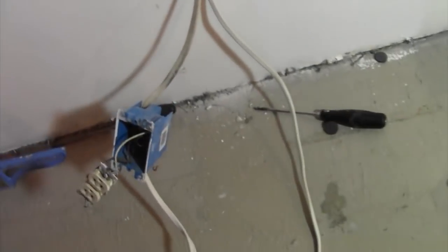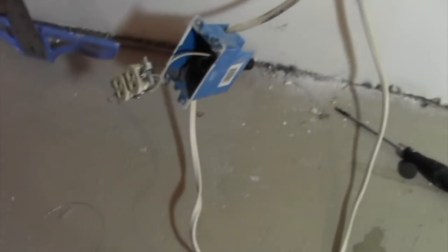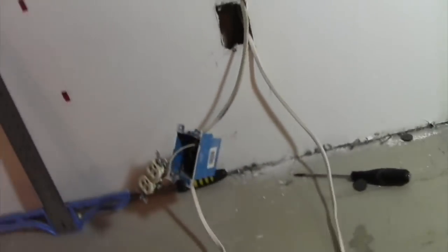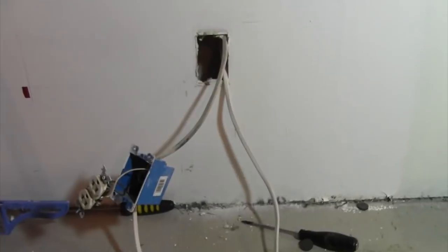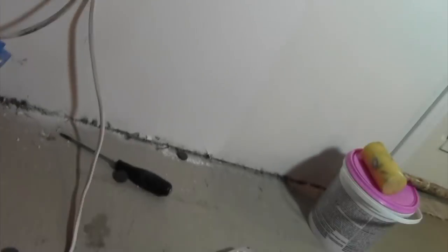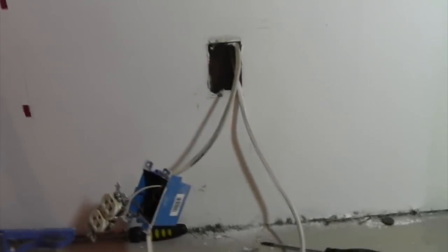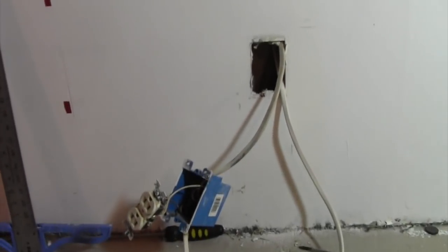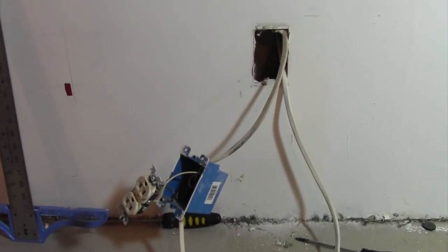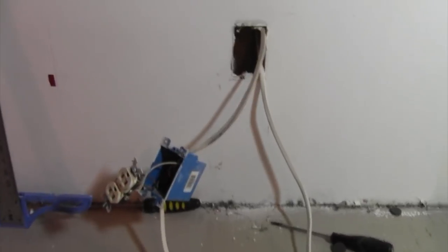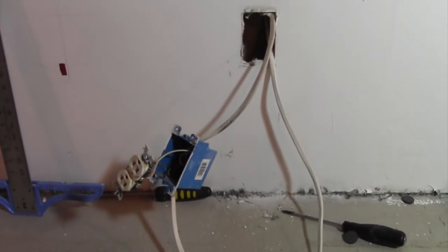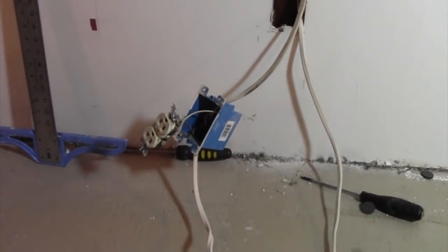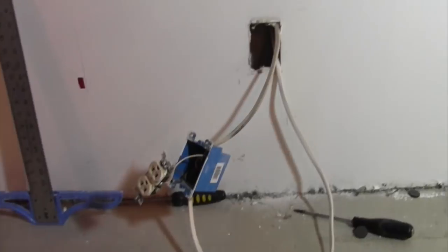Now, what I don't know is which line the power comes from, if it's coming from the top wire or the bottom wire. And I don't know which wire is the feeder and which one is going away. I do know that behind this wall there is a light switch and there's a light, so it probably goes back there. I still have to use both wires to keep everything connected. I haven't shut off the power yet, but I'm going to. So don't fear.